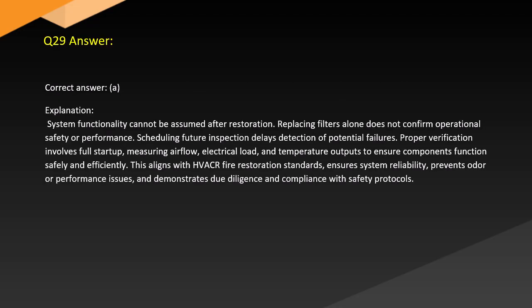Answer. Correct answer: A. Explanation. System functionality cannot be assumed after restoration. Replacing filters alone does not confirm operational safety or performance. Scheduling future inspection delays detection of potential failures. Proper verification involves full startup, measuring airflow, electrical load, and temperature outputs to ensure components function safely and efficiently. This aligns with HVACR fire restoration standards, ensures system reliability, prevents odor or performance issues, and demonstrates due diligence and compliance with safety protocols.